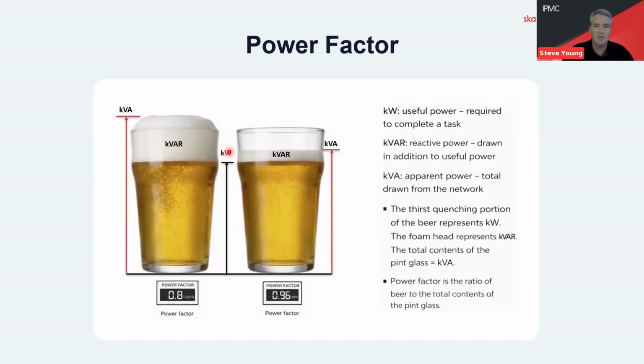On the left-hand side, we have an uncorrected power factor. So we've got a lot of froth on the left-hand side because we're drawing all of that reactive power from the grid. And of course, the summation of those two things is the apparent power, the kVA. We're also charged by apparent power on the bill as available service capacity, so there's another charge associated with that.